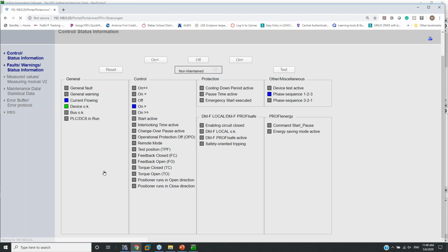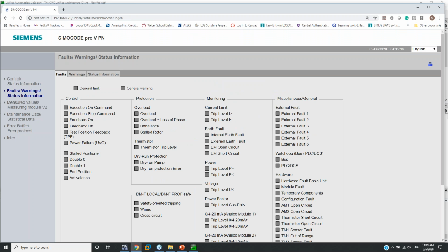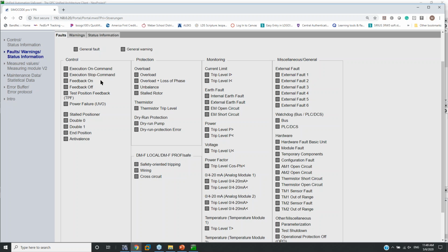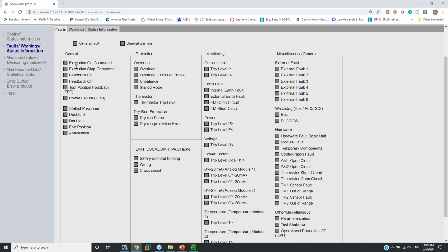Here's my faults. Execution on command, meaning I told it to turn on, but I didn't see any current flowing. So it could give you a quick bump to say, hey, I didn't see any current flowing, so something's wrong. The contactor didn't pull in. Or execution stop command. I had the motor running, I told it to stop, but current kept flowing, which means, in my mind, logically, that one of my contactors welded shut.